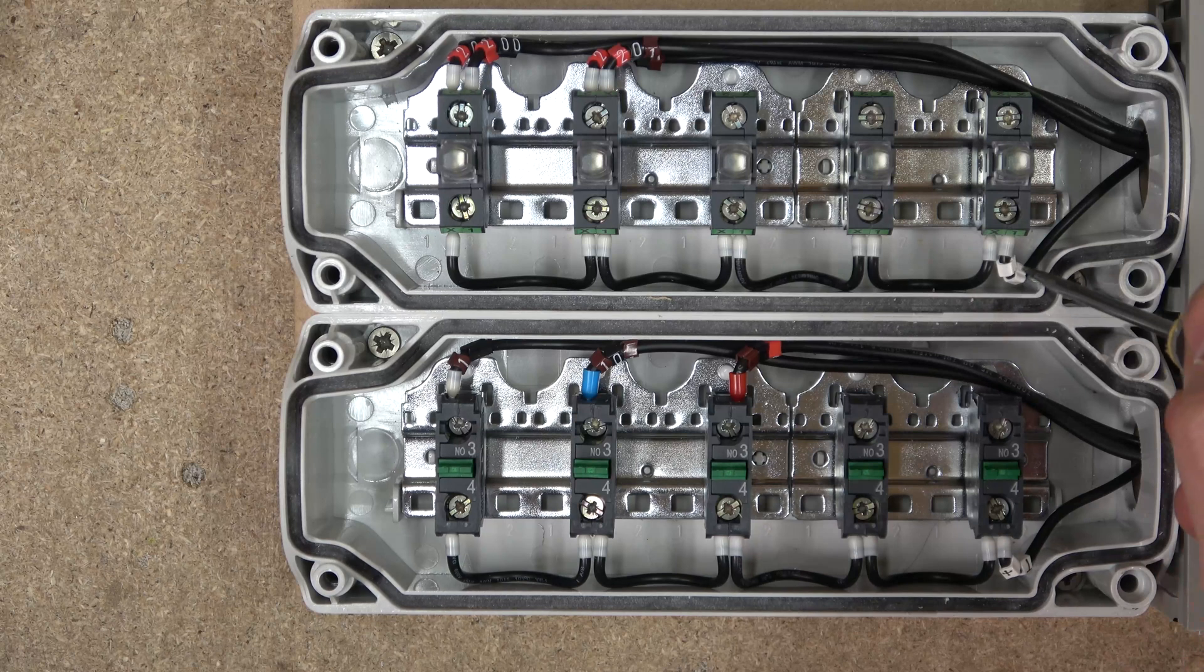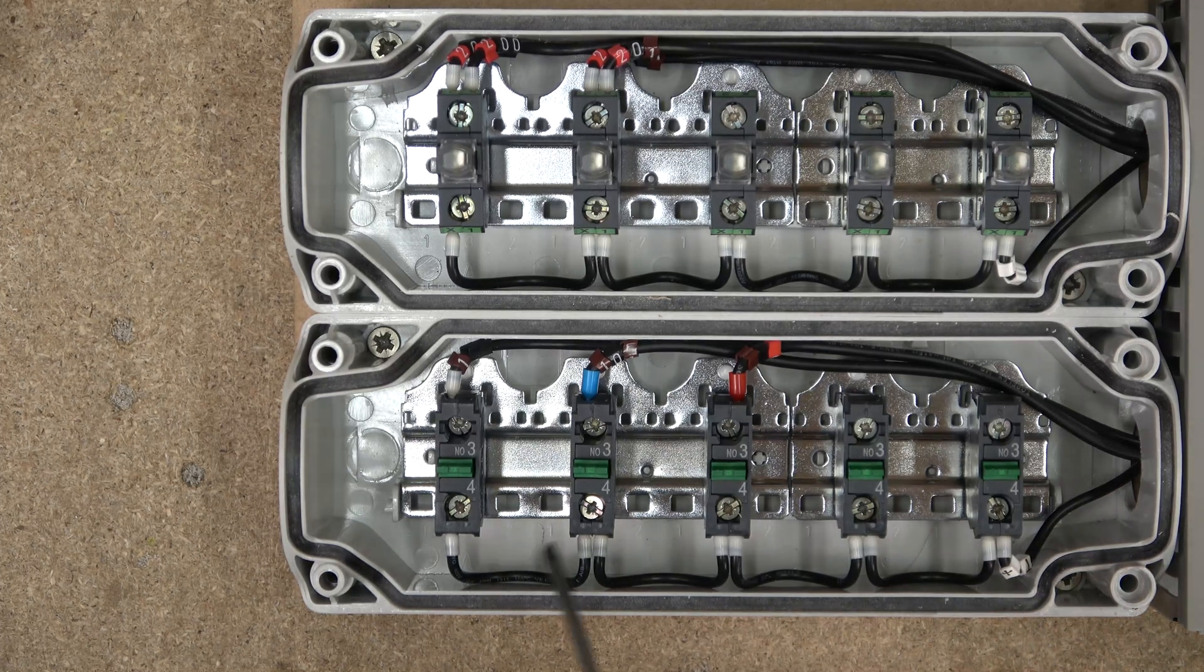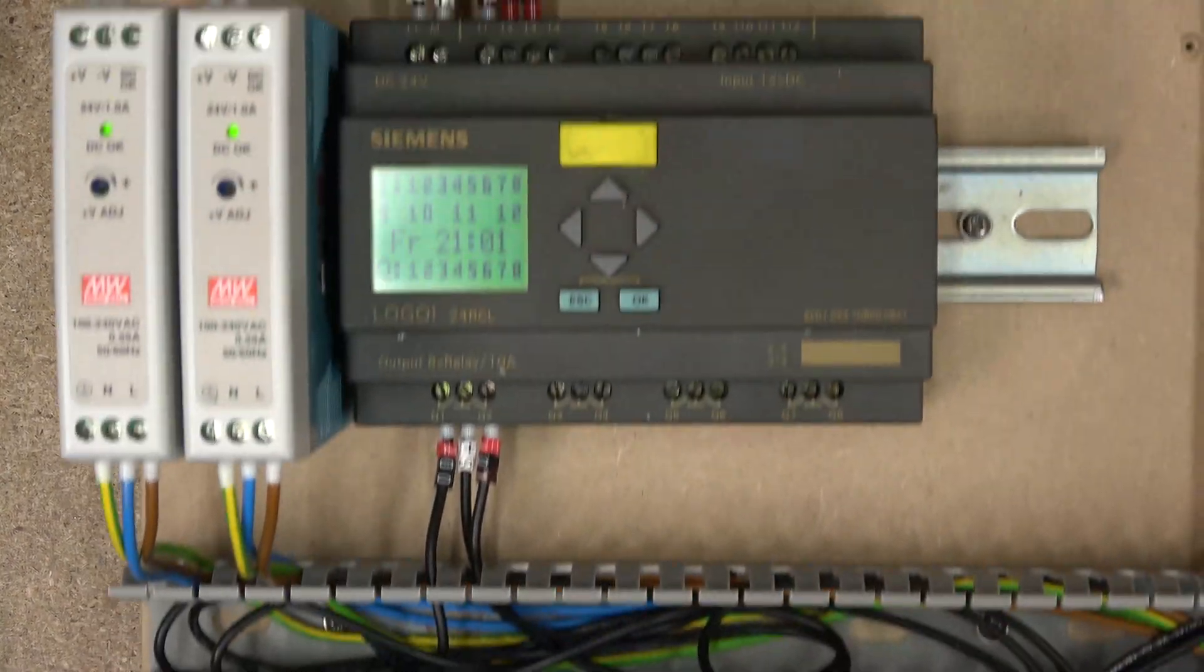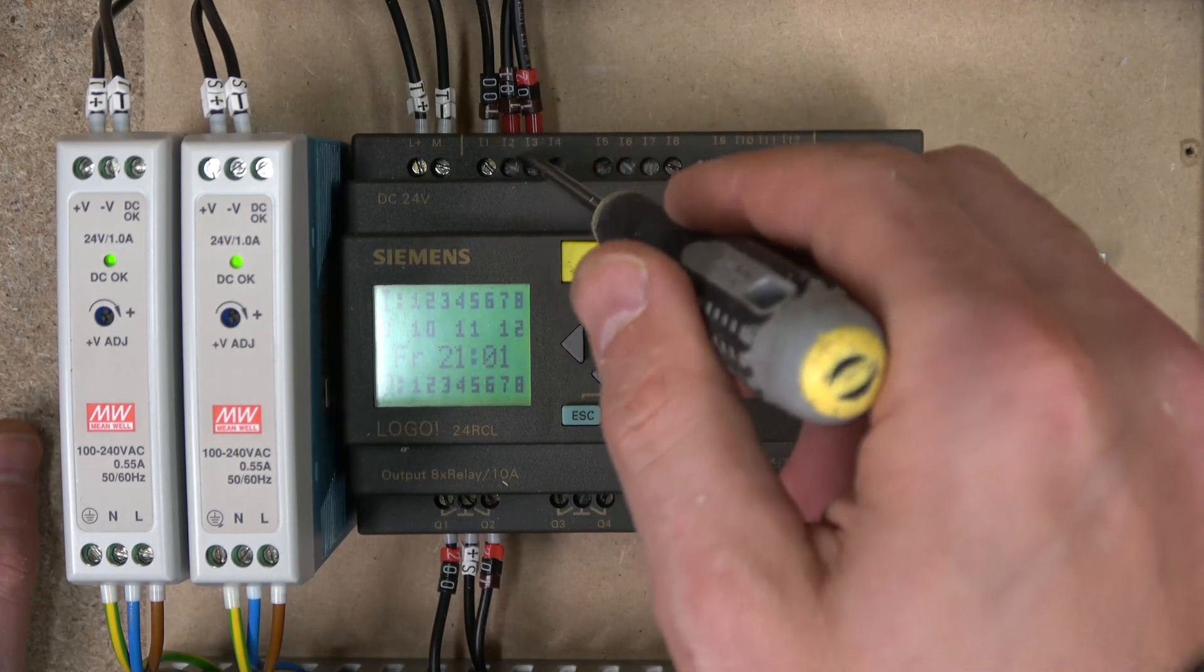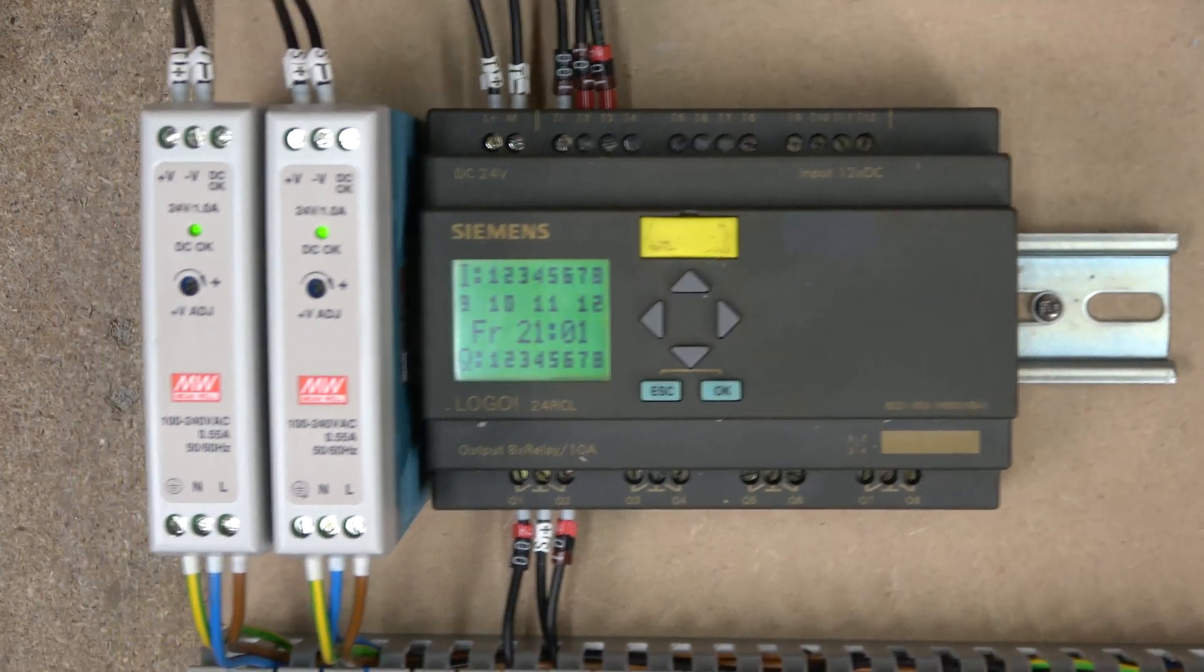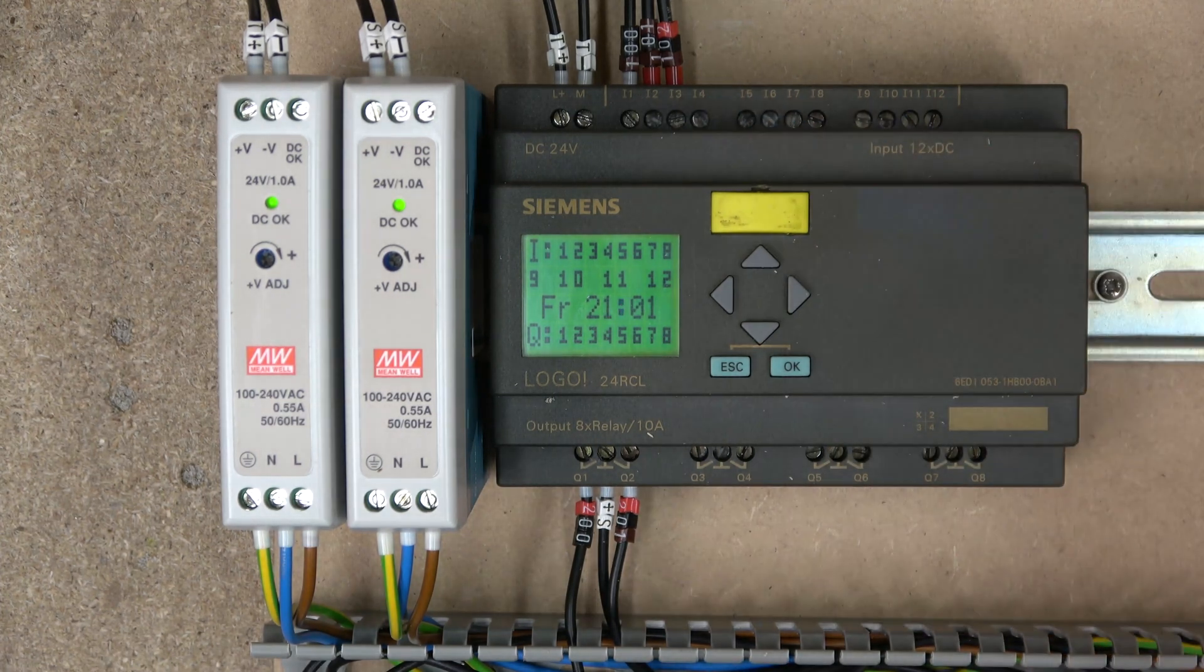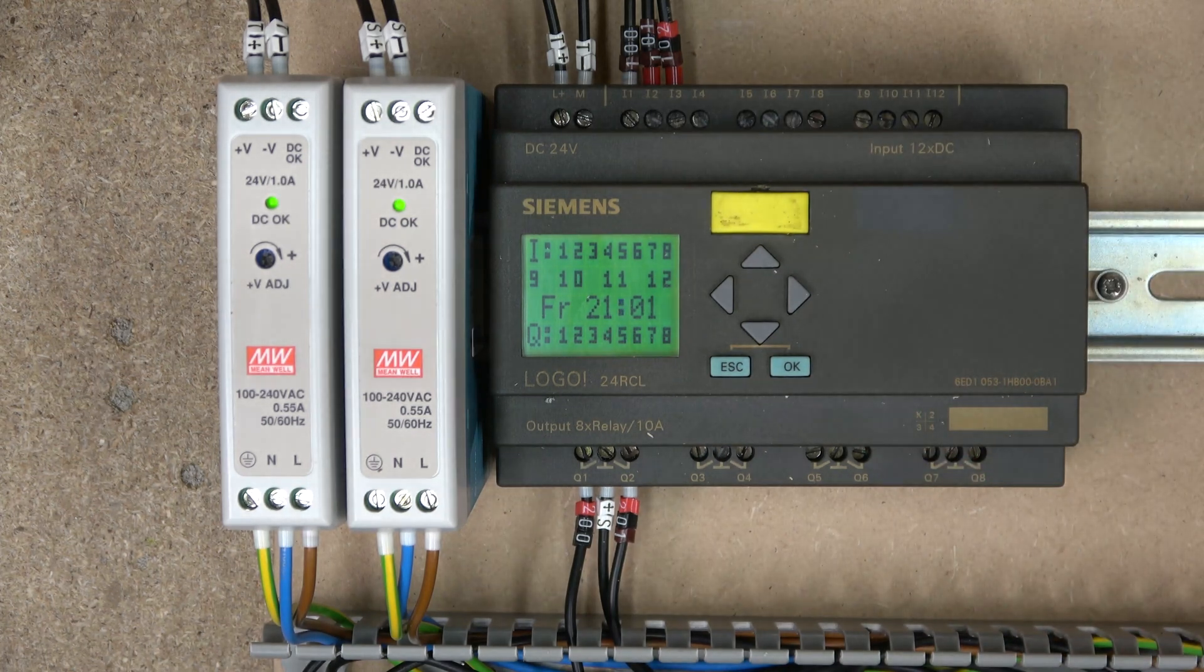As you can see, my T+ is coming over here and it's powering all my buttons. Those buttons will be sending the signals back to the actual controller. Every time the switch is switched, it will be sending signal back to these inputs and those inputs are obviously at 24 volts. That is the key - make sure you use the correct power supply. Make sure you're powering the inputs to the same power source as the controller.